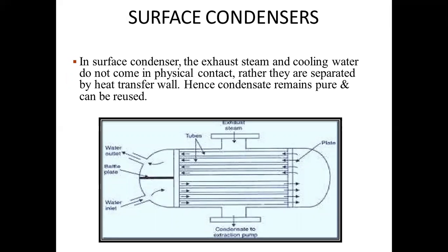In case of surface condenser, exhaust steam and coolant water do not come into physical contact. They are separated by a heat transfer wall, so condensate remains pure and can be reused again and again. There is a diagram which shows a type of surface condenser. You can see in this case exhaust steam enters from the top side while cooling water enters from the side.